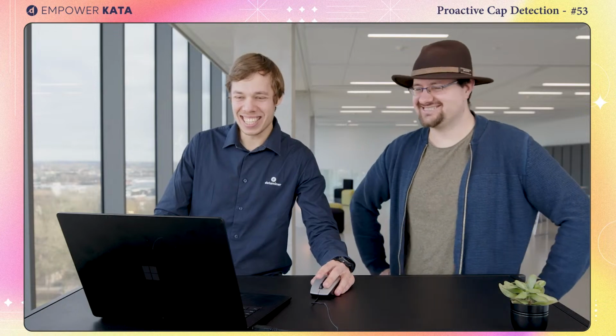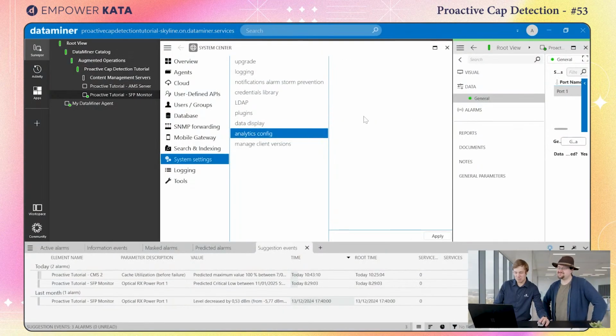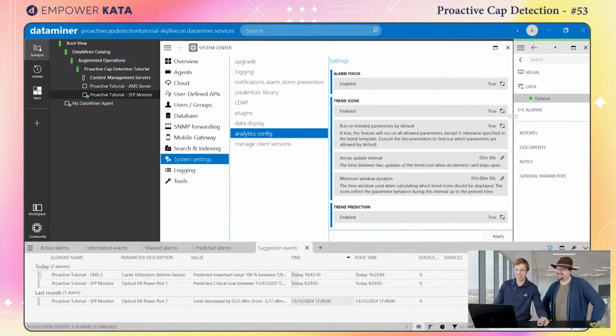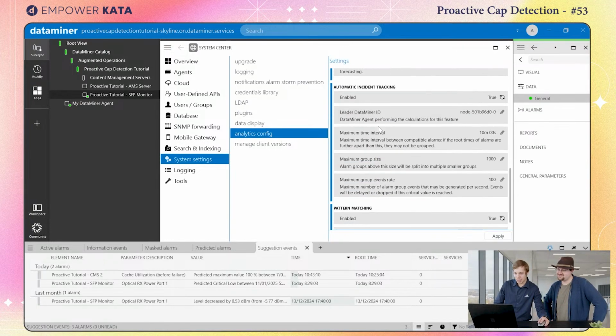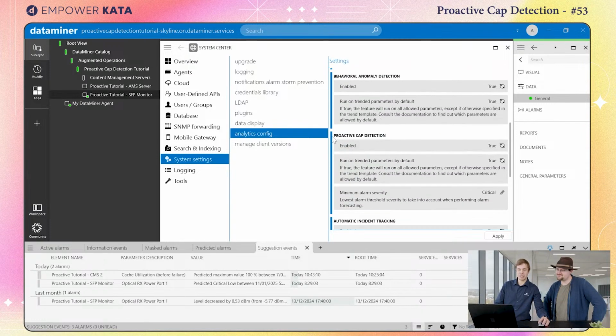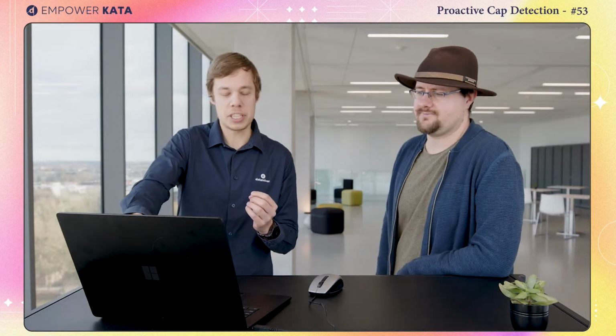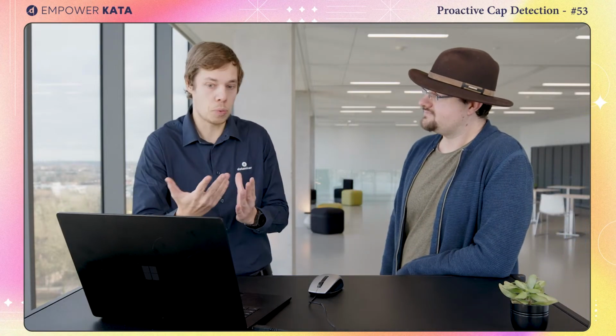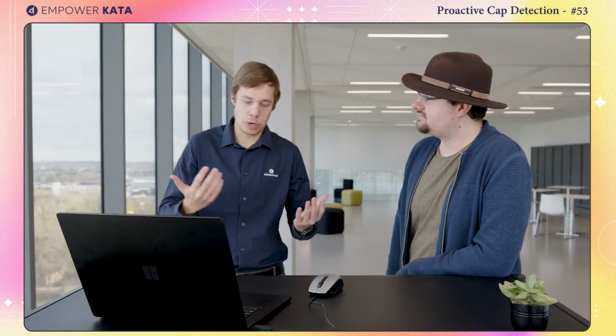Or it's in system settings and then analytics config. And there should be some configuration loading. There we go. And then it's Proactive Cap Detection. And there you can do a bit of configuration. Name, alarm severity. And here you can set minor, and then it will do minor, major, and critical. So it's the minimum. And you can also configure it in the alarm template specifically for a specific parameter, because this is system wide. But if you just want one parameter, you can do that as well.